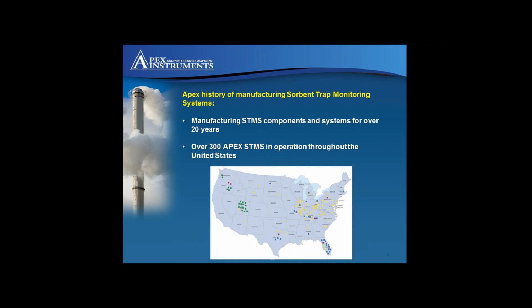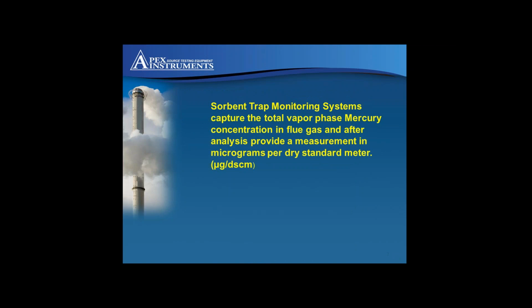Good afternoon, everybody, again. I want to take you through what Sorbent trap monitoring systems are all about. They capture the total vapor phase mercury concentration in the flue gas, and after analysis they provide a measurement in micrograms per dry standard cubic meter. Method 30B is the reference method for relative accuracy test audits, RATAs, and may be used to determine compliance for a mercury CEMS or a continuous Sorbent trap sampling system. It is intended for use under relatively low particulate conditions.